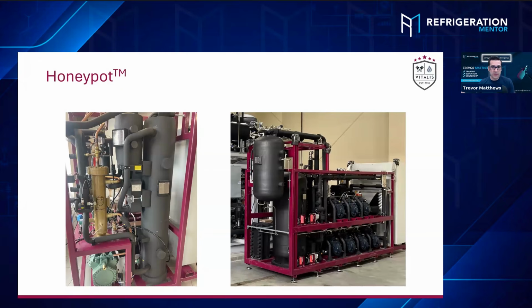Okay, perfect. So the whole system's on evacuation, but when we isolate the oil reservoir, when we pull the oil into it, is that correct? No, the whole system can be in operation. Yeah, but I mean on first startup. So it's an empty system. Yeah. Okay, so your empty system right now. We're at first startup. Everything's in a vacuum right now because we're just talking about first startup. You isolate the reservoir, you fill it up to half full. You take the vac pump off, then you open up the oil reservoir at this point, and then it'll feed to all the transfer blocks. I just want to make sure the steps on a startup are correct when they're doing it.